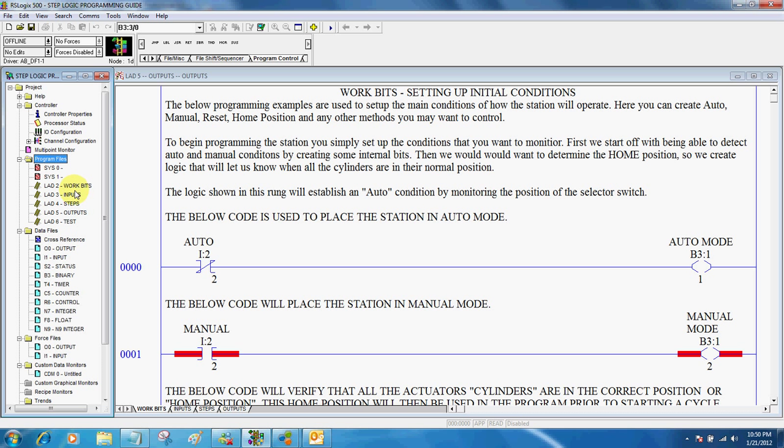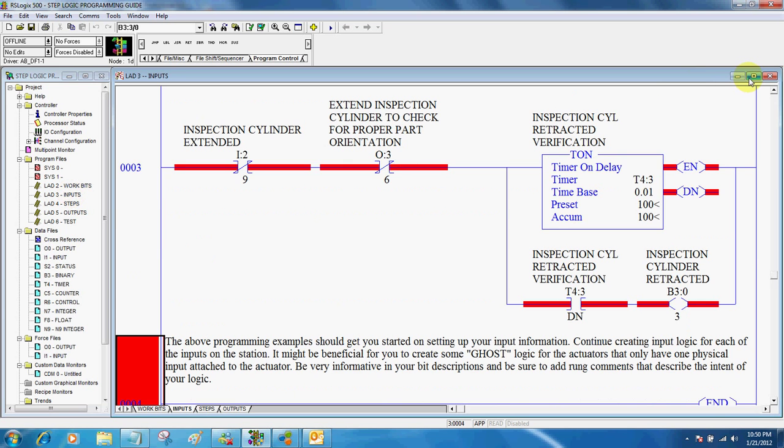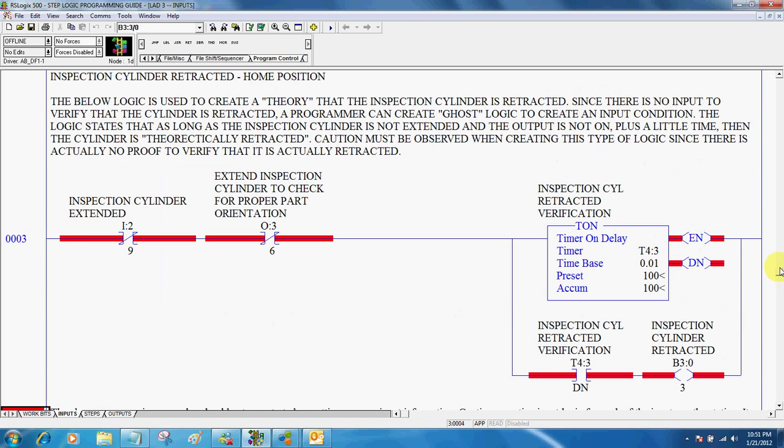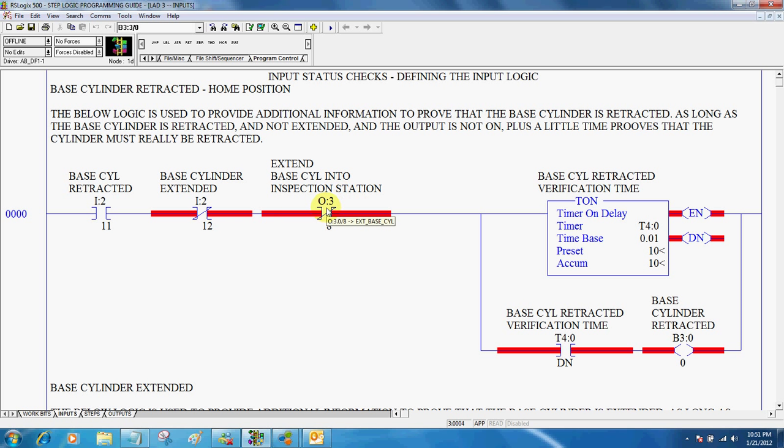One of the first things that I start with is my input logic. I'm going to go ahead and activate that, get that up here before we can take a look at it. I just page title it as Input Status Checks and defining my input logic. So here, we allow the programming of our logic to give us some additional control. So if the base cylinder is retracted and the base cylinder is not extended, and the output to extend it is not on, plus a little bit of time, tells us that the base cylinder actually is retracted.